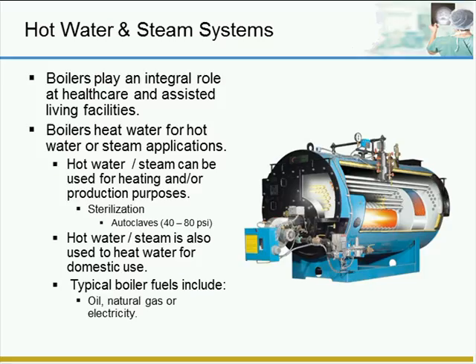You have high and low pressure units. High-pressure steam is anything over 15 PSI, and anything over 160 PSI of water will be considered high pressure as well. Typically, you won't see any high pressure water systems. Temperatures are usually in degrees Fahrenheit. Capacities of boilers will be in horsepower, pounds per hour, or if you have a smaller electric unit, it will be in kilowatts. Typical fuels used will include natural gas, oil, propane, and not typically, but sometimes you'll find biomass boilers, which will burn fuel or trash or a combination. The picture here is a fire tube, three-pass high-pressure boiler. This is a typical boiler you'll find at a hospital or a medical facility.